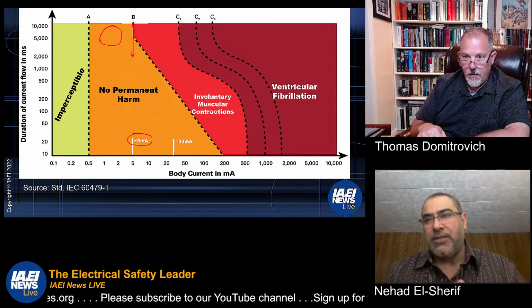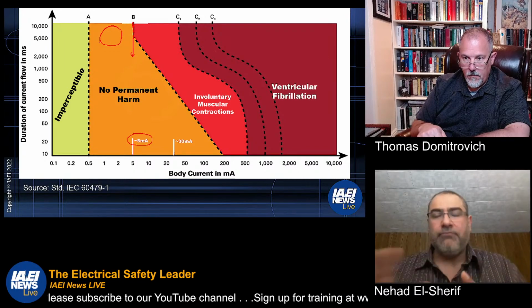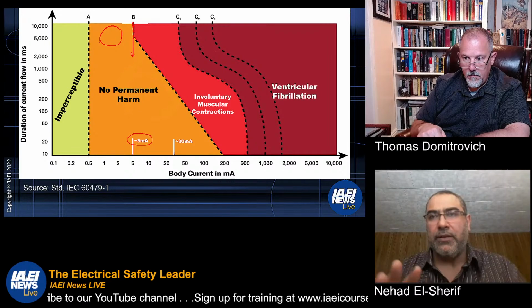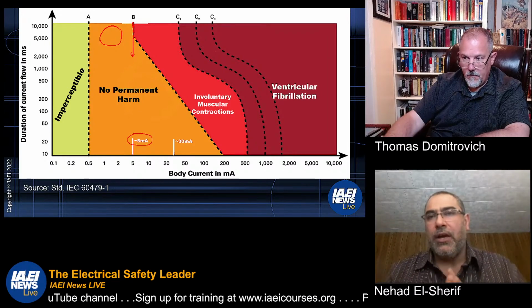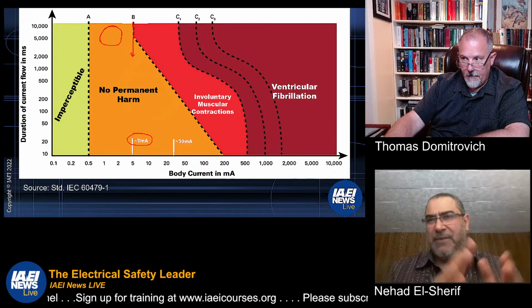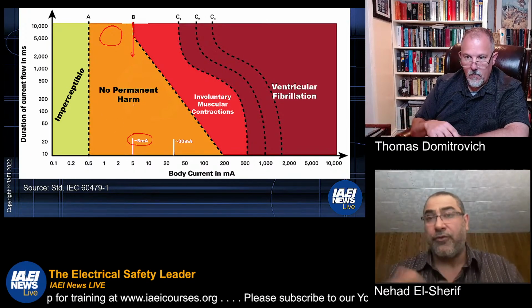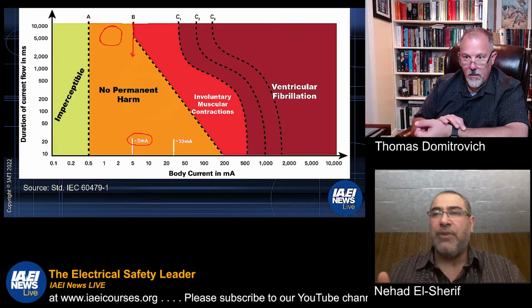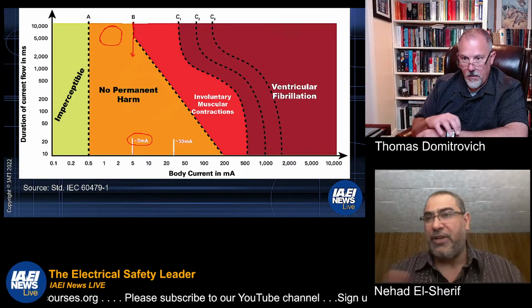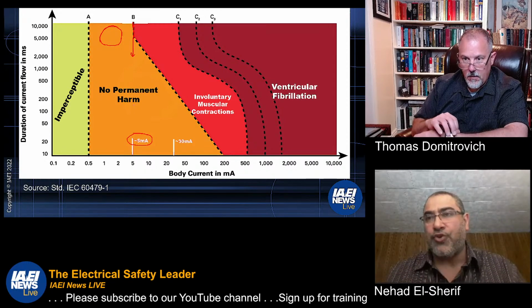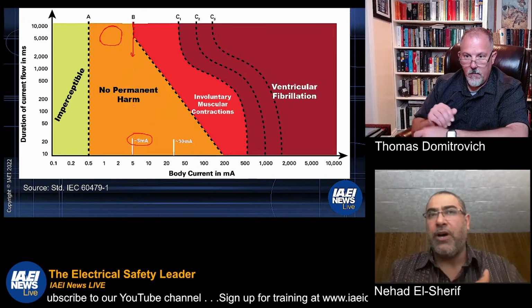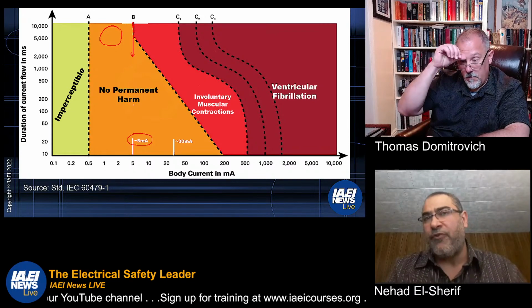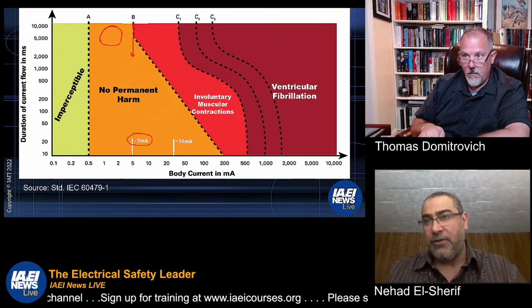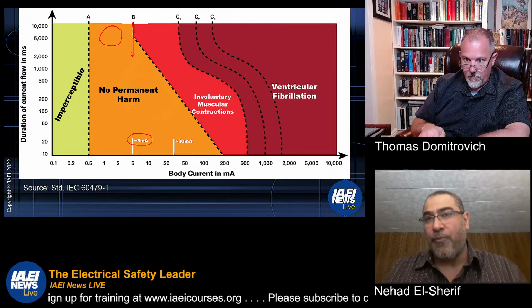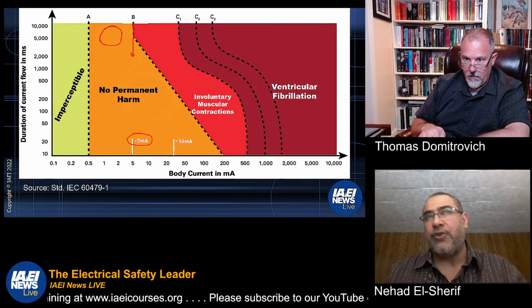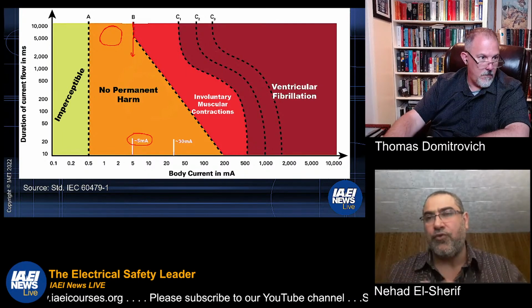And it was designed because usually the let go threshold, again for the 90th percentile of healthy people with dry skin and so forth, is around 8 to 10 milliamps. I guess 8 is maybe for kids and women, and it goes up to 10 for adult males. So 5 is much lower than this limit, which means you'll have no permanent harm. You can let go of the circuit. You don't need a GFCI to interrupt power for you. That's why Tom and I initially said that Class A GFCIs provide both let go and ventricular fibrillation protection. At that point you can still let go, but the device would interrupt power maybe quicker than you let go. So it's still providing these two kinds of protection.